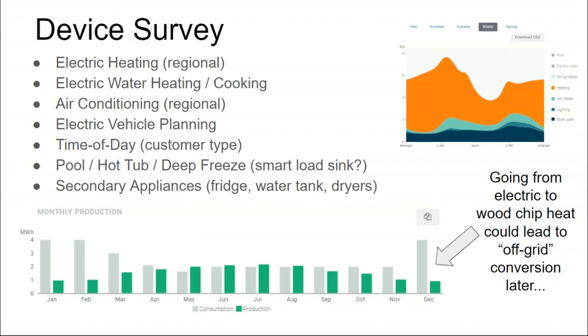I had an off-grid house where they were using high-end energy efficient heat pumps that normally operate at 3 or 4 kilowatts of power. But inside the heat pump there's an electric heating strip that's 10 kilowatts in size for each of them. There was an option to get this strip down to 5 kilowatts, but no one picked that up. So when the electric heating strips come on, this home load, which is normally 5 or 6 kilowatts, skyrockets up to 35 or 40 kW. So if you don't have 35 or 40 kW of inverter capacity, the system's going to turn off.